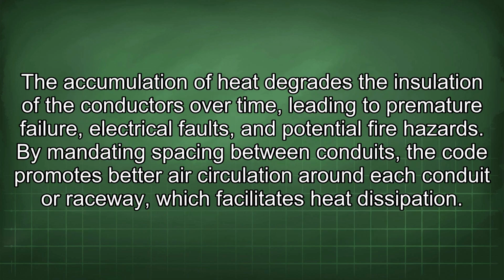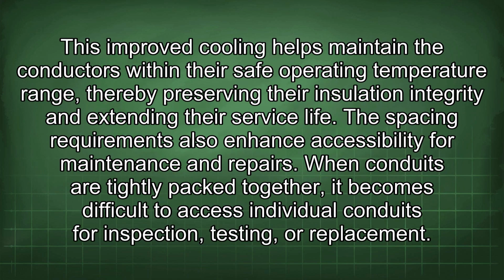The accumulation of heat degrades the insulation of the conductors over time, leading to premature failure, electrical faults, and potential fire hazards. By mandating spacing between conduits, the code promotes better air circulation around each conduit or raceway, which facilitates heat dissipation. This improved cooling helps maintain the conductors within their safe operating temperature range, thereby preserving their insulation integrity and extending their service life.